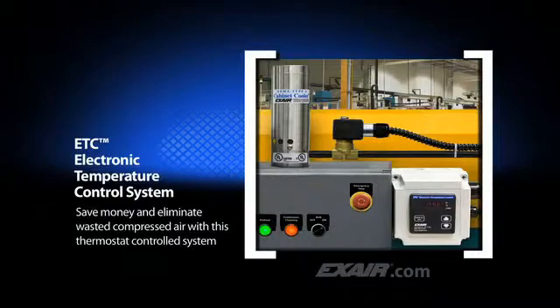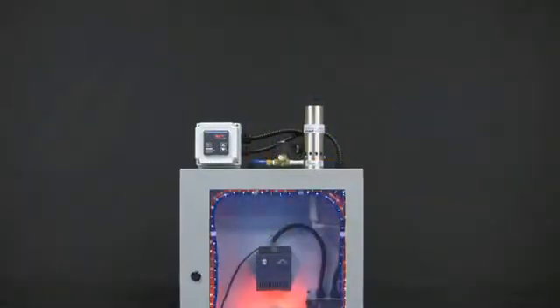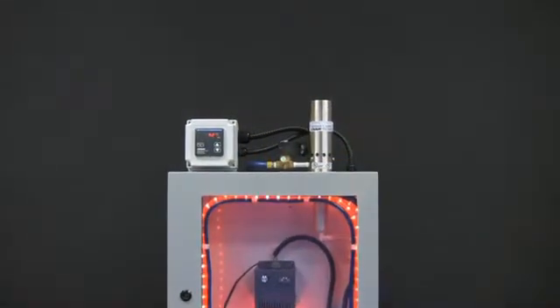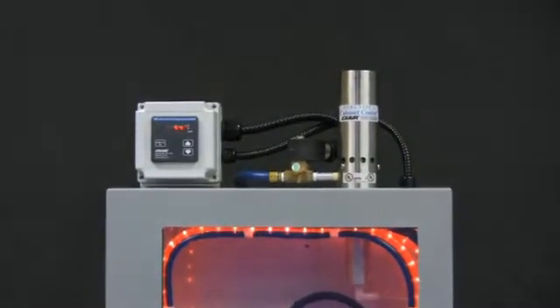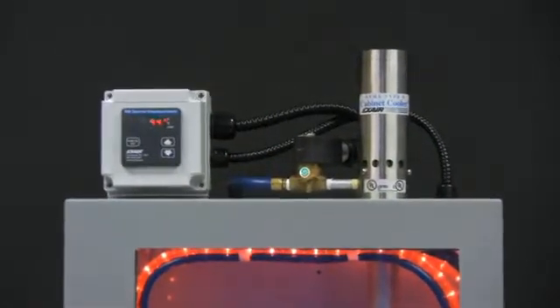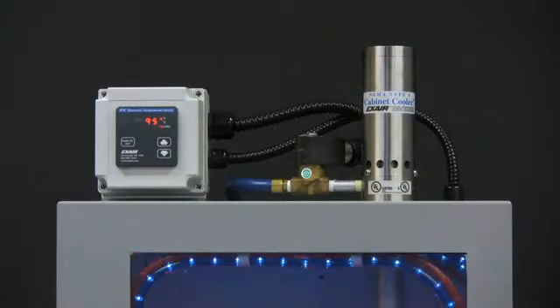The temperature inside the enclosure is constantly monitored by a quick response thermocouple, with an LED display on the ETC that shows either degrees Fahrenheit or degrees C. The control activates the included solenoid valve when the temperature setting has been exceeded. The ETC is also CE compliant to assure safe operation.